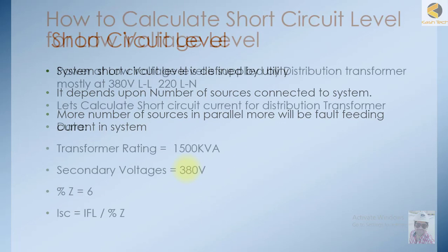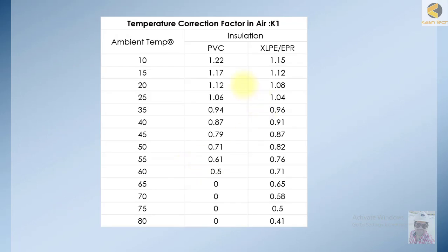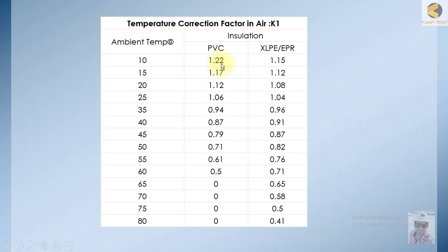This is the temperature correction factor K1. As discussed, if the ambient temperature in a very cold area cannot go beyond 10 degrees, the capacity of the cable increases — it goes to 1.22. So if you are using a PVC cable rated at a certain ampere, at 10 degrees the capacity will be multiplied by 1.22, and XLPE capacity is multiplied by 1.15.